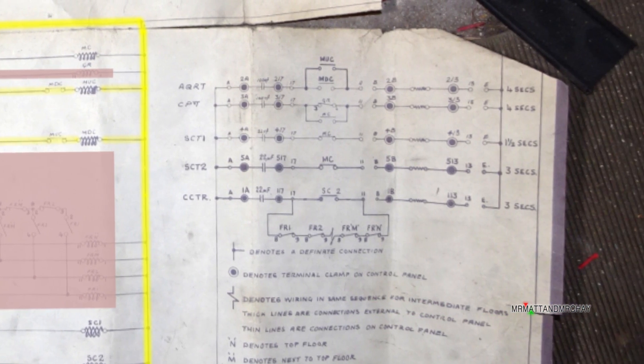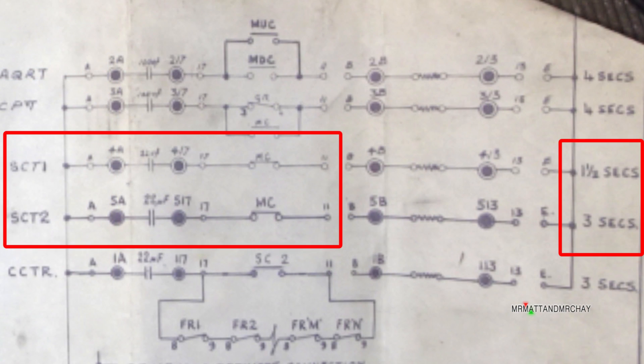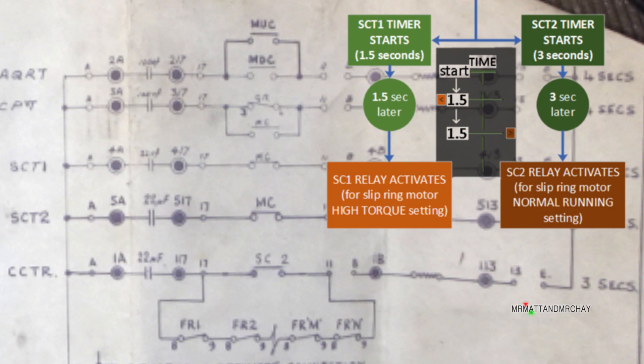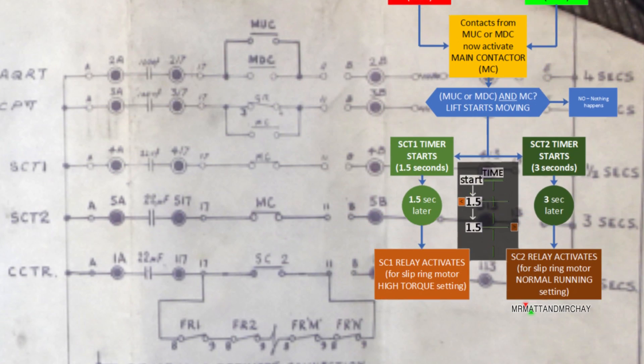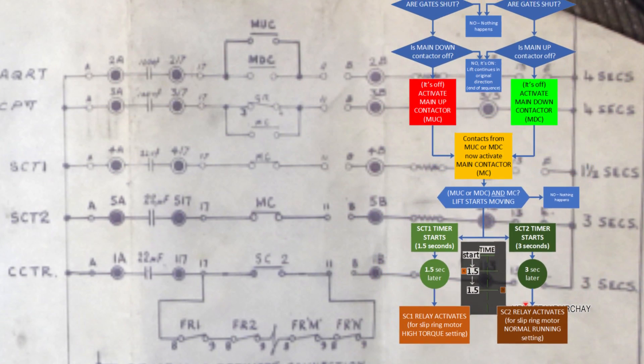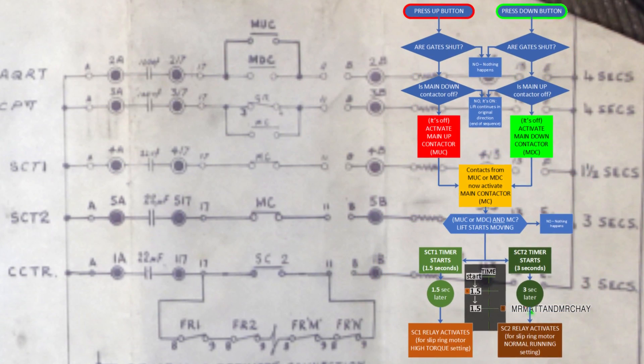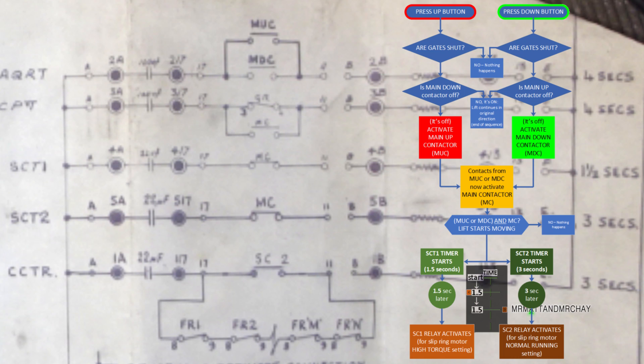Moving to the right, these are a collection of timer circuits, but it's these that I want to focus on. When the main contact is activated, two timers are activated together. These are SCT1 and SCT2. SCT1 delays the first slip ring motor relay for 1.5 seconds. After a further 1.5 seconds, timer SCT2 activates relay SC2. Relays SC1 and SC2 control the slip ring motor, which is coming up in a moment.